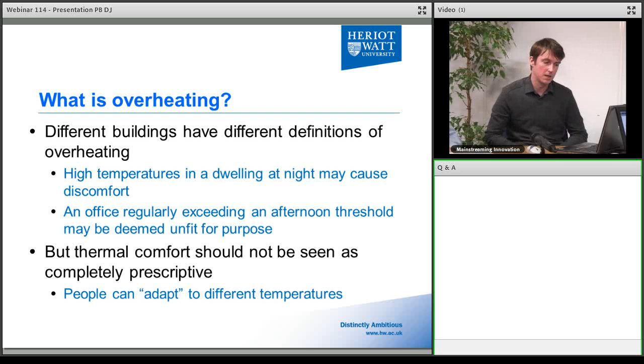For a future climate, in extreme examples we may have undersized cooling plants, which would be a problem because you can't get to your desired temperature inside the building. But there's also the case that your cooling plant might be large enough, but because you're dealing with a different cooling load profile due to climate change, perhaps the operation of that plant is no longer optimum.